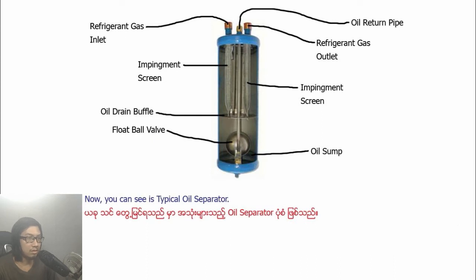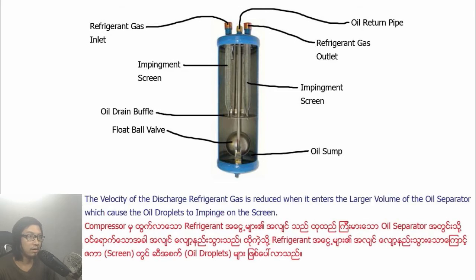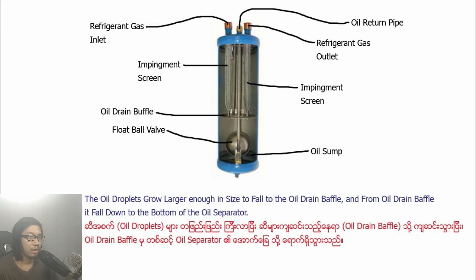Now you can see a typical oil separator. It is an impingement type oil separator. Screens in the upper half cause small particles of oil to collect and form larger ones. The velocity of the discharge refrigerant gas is reduced when it enters the larger volume of the oil separator, which causes the oil droplets to impact on the screen. The oil droplets coalesce on the inside and fall to the oil drain baffle, and from the oil drain baffle it falls down to the bottom of the oil separator.